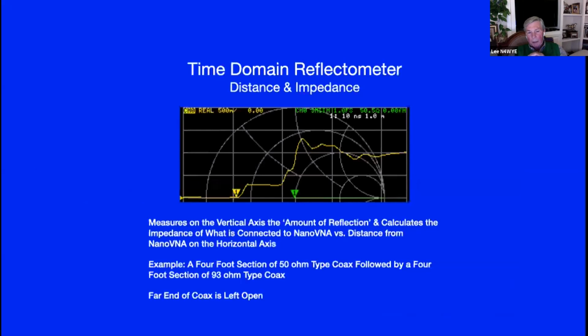Here's a time domain reflectometer perspective. If you look here at this piece of coax, here's where it changes from 50 ohms to 93 ohms, and here it's actually open on the end. So you can get an idea of where the instances of impedance change are along, say, a bad connector or a connector with water in it, and you can actually get the distance in feet or meters.